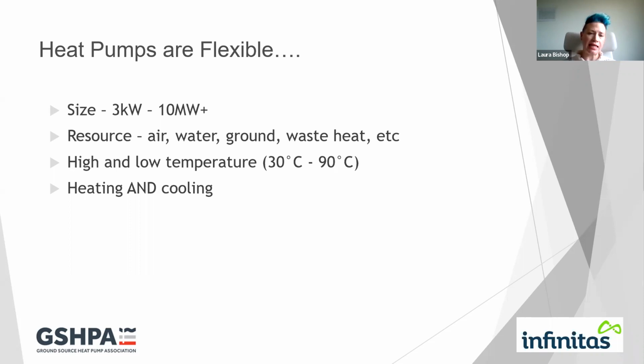I was talking to somebody yesterday who actually replaced an air to water chiller with a water chiller to do, I think it was a cooling plant, a food storage plant. So they're still doing the same amount of cooling as they were doing before, but instead of chucking all the heat out to air, they're now extracting that heat from the reject heat and putting that into the heating of the building. They no longer need to have, it was actually LPG boilers, so they've got rid of the LPG boilers, and the water source cooling system is now doing all of the heating and most of the cooling in the factory. They're great for new build and retrofit.